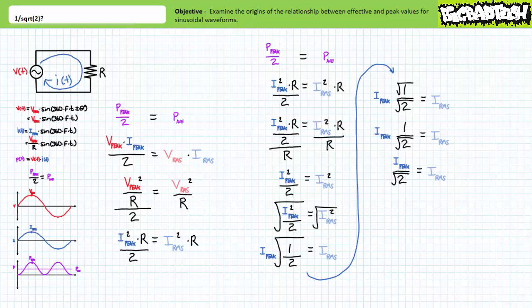Given an effective value of 120 volts, it can be easily demonstrated this correlates to a peak value of 169.7 volts. Like I said, don't mess this simple relationship up. Peak is greater than the effective value; the effective value is less than peak. Unless explicitly directed otherwise, you can assume all AC measurements are expressed in terms of effective or RMS values.